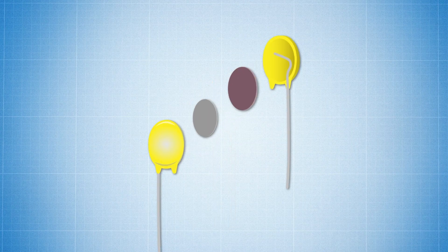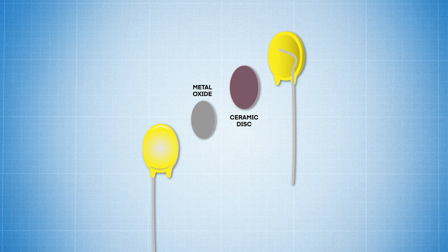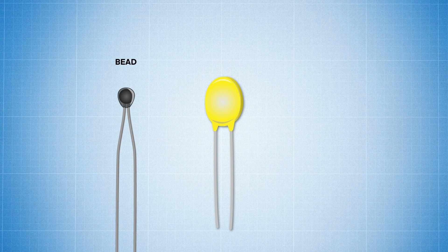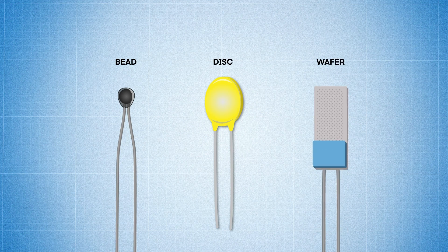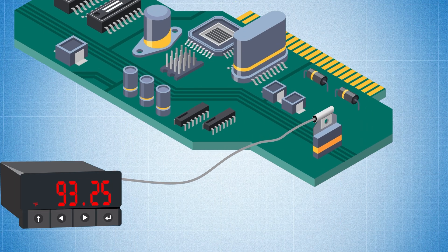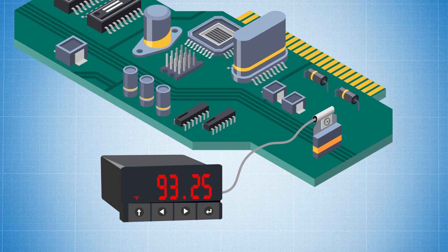Thermistors consist of a metal oxide semiconductor pressed into a small bead, disc, or wafer that's coated with epoxy or glass. And since thermistors are constructed of semiconductor materials, they provide the best sensitivity of any measurement device and are ideal for measuring smaller temperature changes.